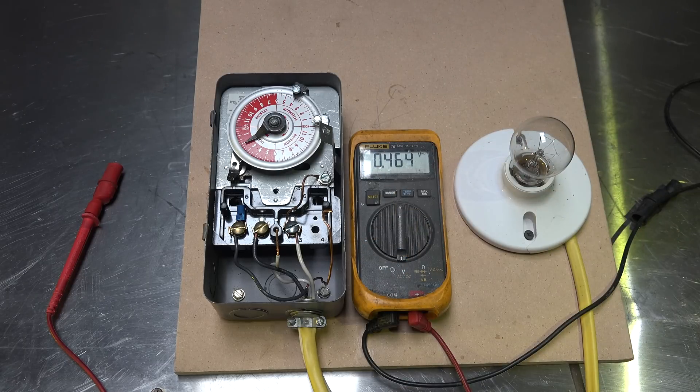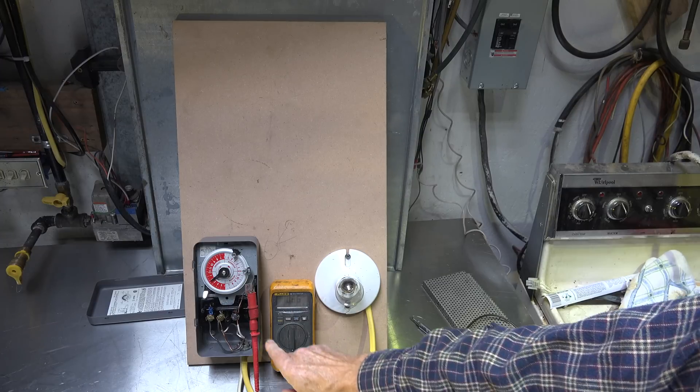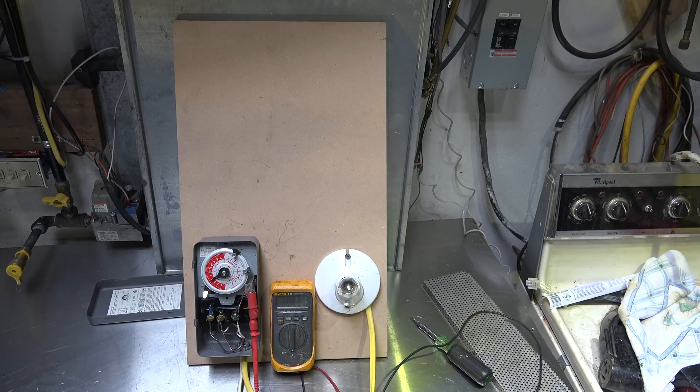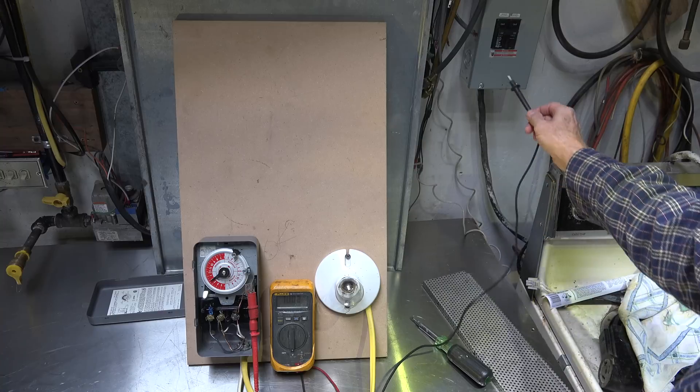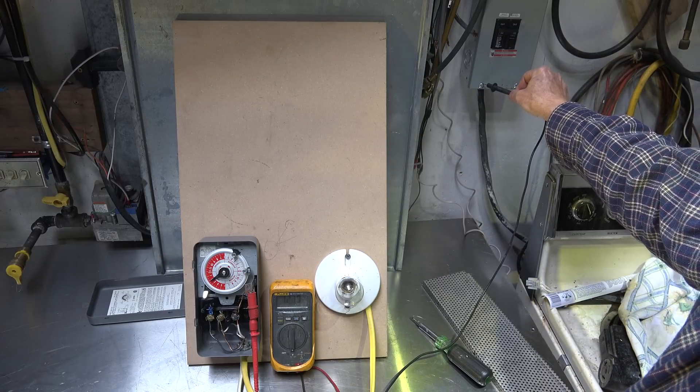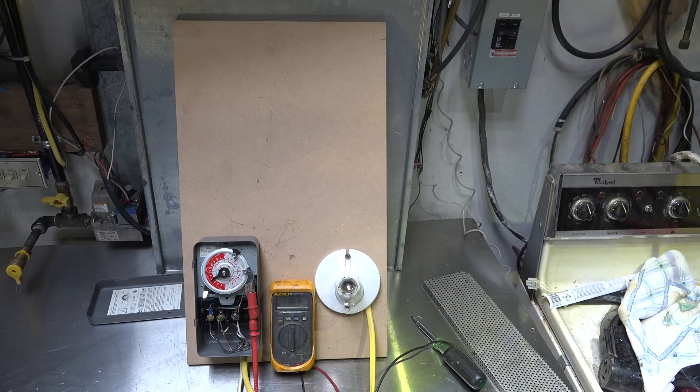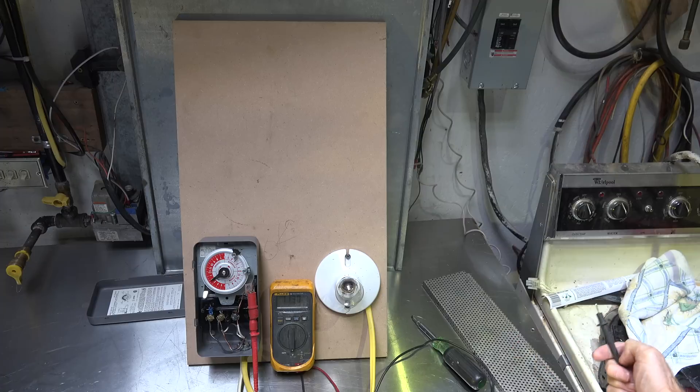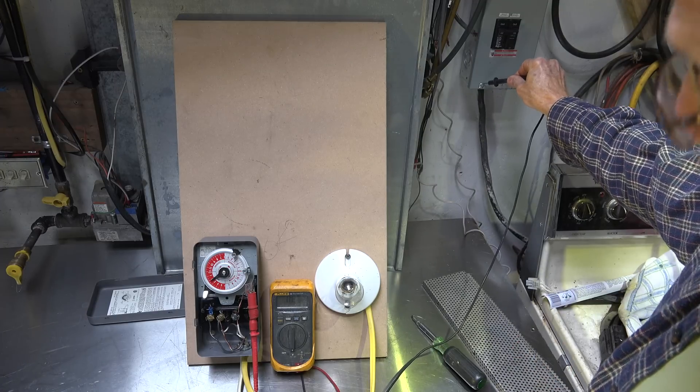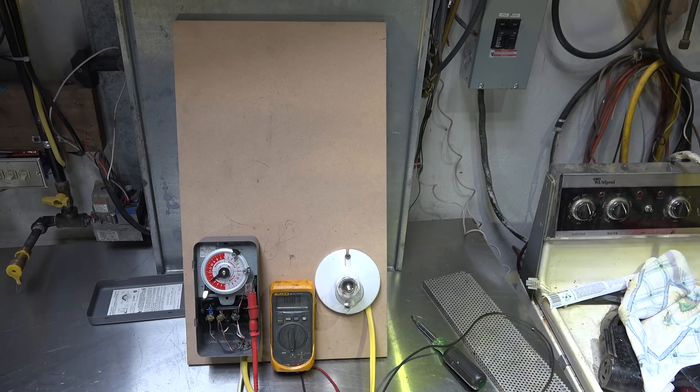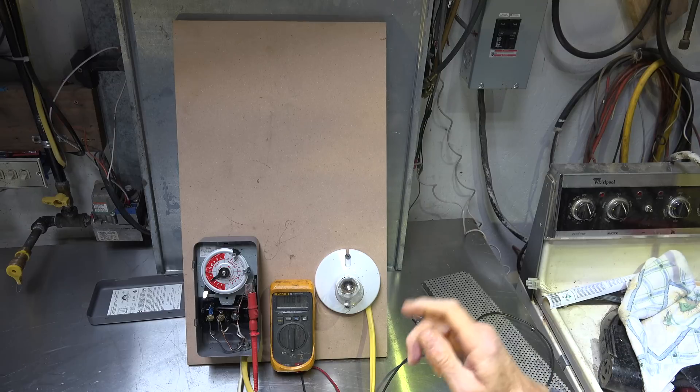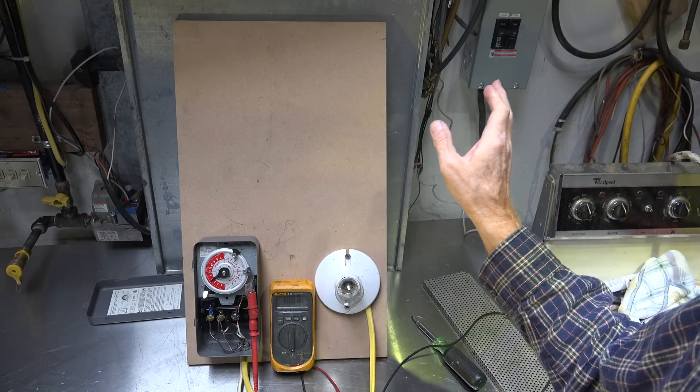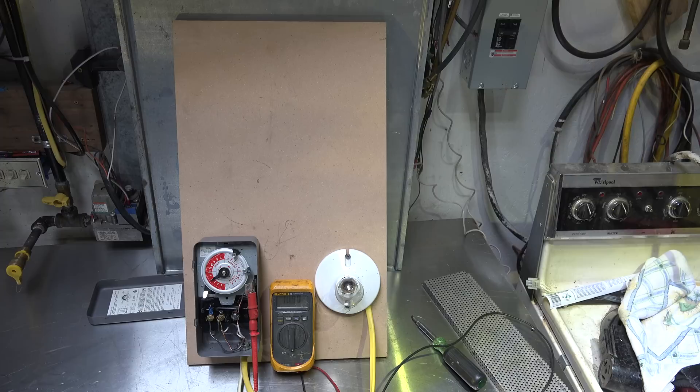I'm gonna give you a further demonstration. I have taken my meter lead here and put it to the chassis of this box. And then I've got another disconnect, service disconnect here. And if I touch it, I've got 120 volts. So if I were to touch the chassis of this box and standing in water touch a metallic ground of some sort, this is why we separate the ground from the neutral in the sub panel. If the conditions were correct, you could end up getting a shock by touching this thing and being grounded with some other part of your body. That's the reason for it. I hope it makes sense.